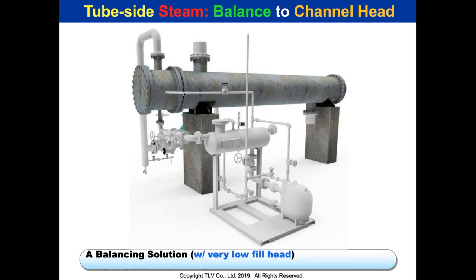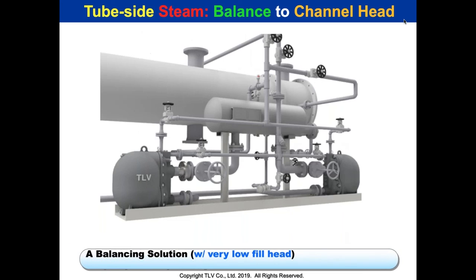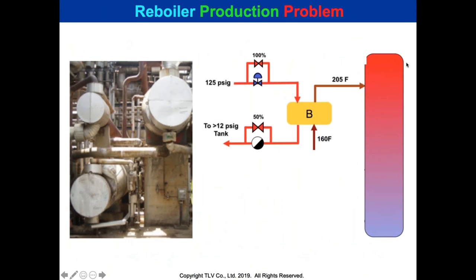That's the stringent balance-to-channel-head requirement. For a low-level reboiler close to grade, we put a loop keeping the line below the tube bundle, use center-fill with an oversized reservoir feeding three pumps — all feasible within narrow footprints.